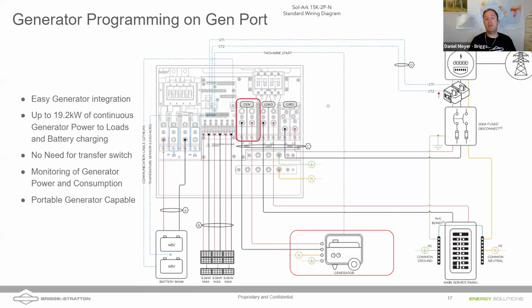Yeah, and we're going to show you here on an upcoming slide exactly how to program that value so you don't overload the generator. One nice thing about this is that there's no transfer switch. As I mentioned, the transfer switch is built into the Sol-Ark, so we're not needing that extra piece of equipment. If you do come out to a site that already has an existing transfer switch, we're going to show you here in a little bit how that might look.